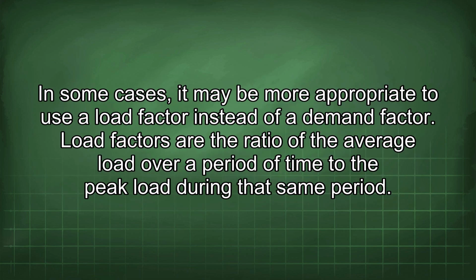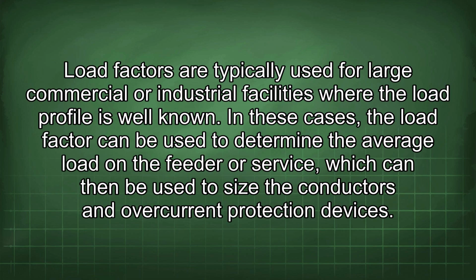In some cases, it may be more appropriate to use a load factor instead of a demand factor. Load factors are the ratio of the average load over a period of time to the peak load during that same period. Load factors are typically used for large commercial or industrial facilities where the load profile is well known. In these cases, the load factor can be used to determine the average load on the feeder or service, which can then be used to size the conductors and overcurrent protection devices.